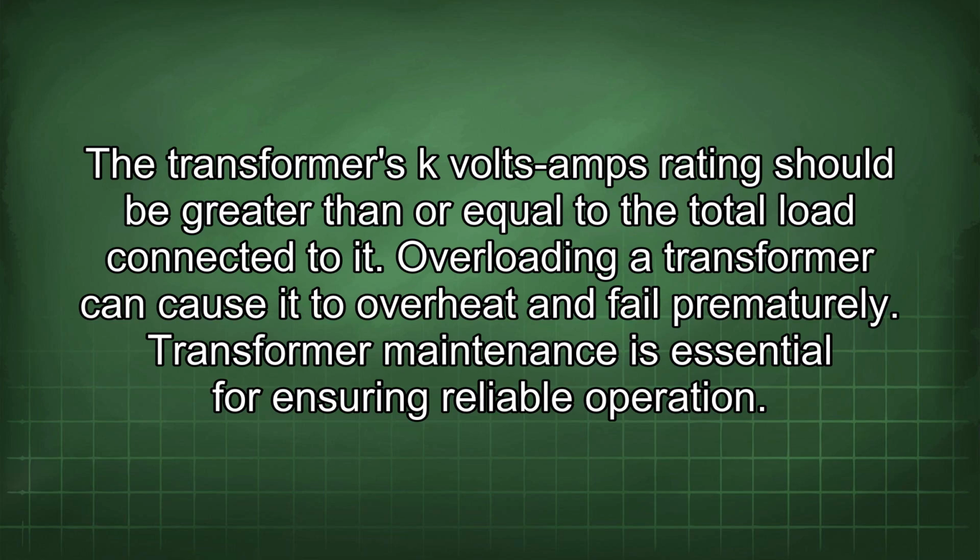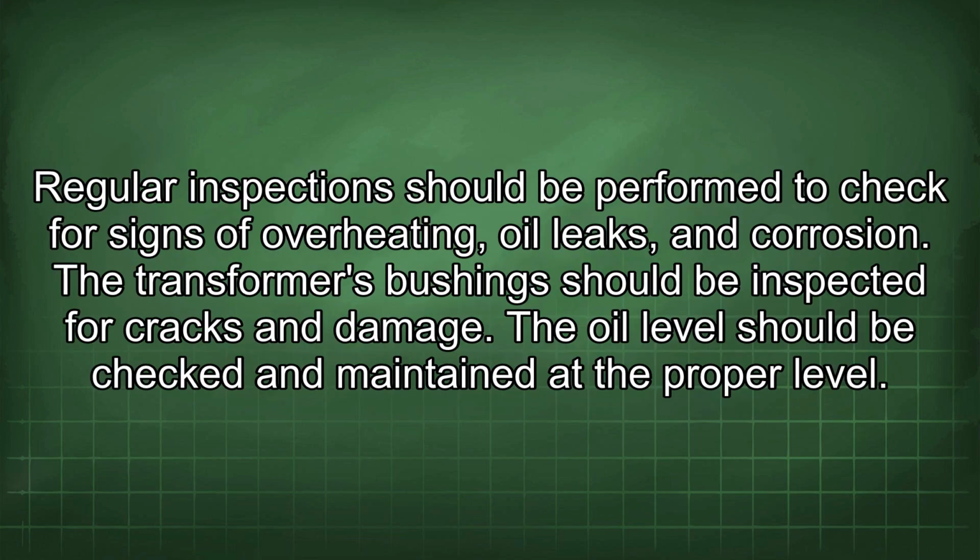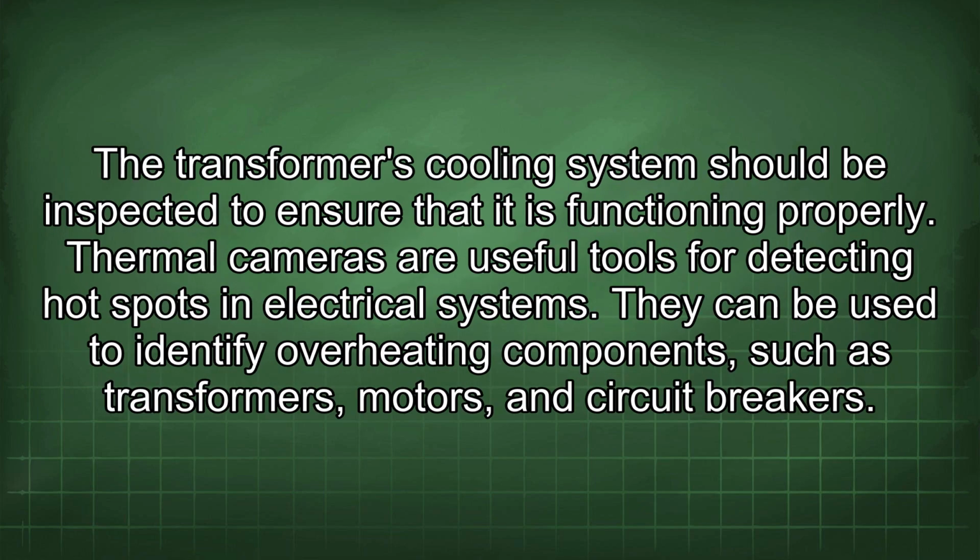Transformer maintenance is essential for ensuring reliable operation. Regular inspection should be performed to check for signs of overheating, oil leaks, and corrosion. The transformer's bushings should be inspected for cracks and damage. The oil level should be checked and maintained at the proper level. The transformer's cooling system should be inspected to ensure that it is functioning properly.